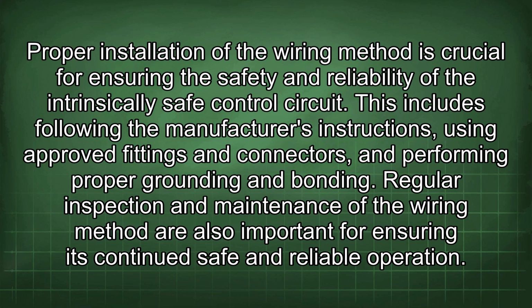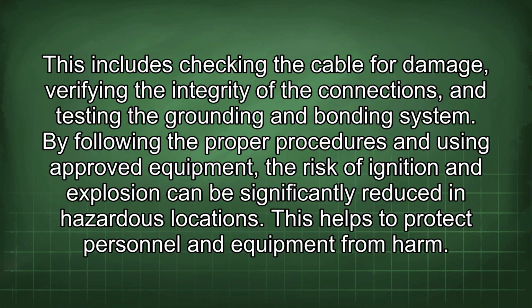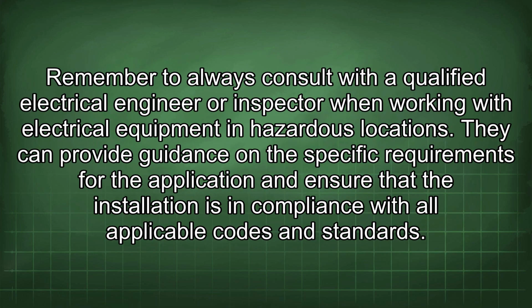Regular inspection and maintenance of the wiring method are also important for ensuring its continued safe and reliable operation. This includes checking the cable for damage, verifying the integrity of the connections, and testing the grounding and bonding system. By following the proper procedures and using approved equipment, the risk of ignition and explosion can be significantly reduced in hazardous locations. This helps to protect personnel and equipment from harm. Remember to always consult with a qualified electrical engineer or inspector when working with electrical equipment in hazardous locations. They can provide guidance on the specific requirements for the application and ensure that the installation is in compliance with all applicable codes and standards.